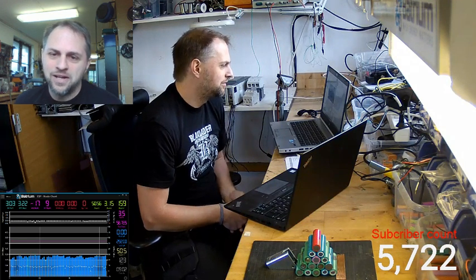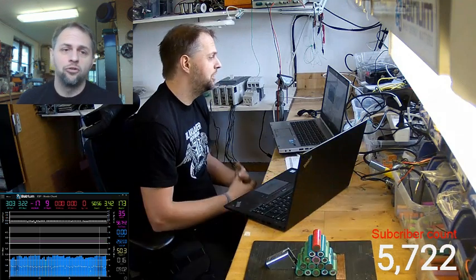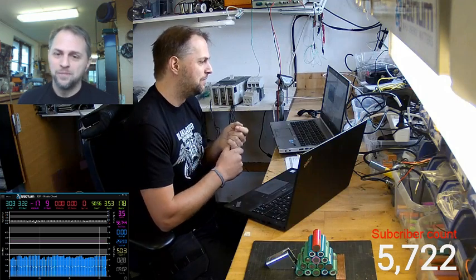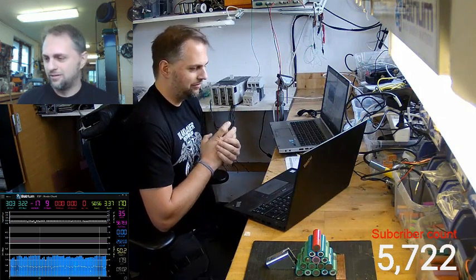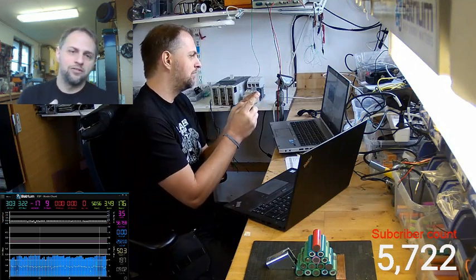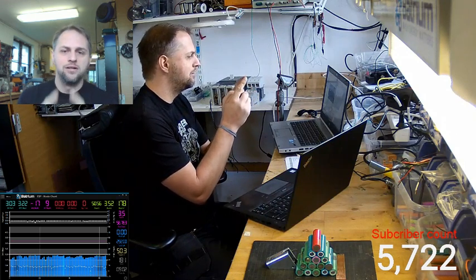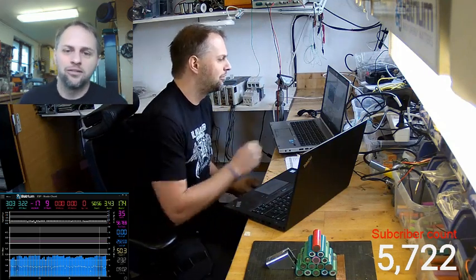The 48 volt APC UPSs are a lot easier to handle than the 192 volt. 48 volt in general is a lot safer to handle than above 150 volt. If you haven't looked into it on YouTube, search for Jacob's ladder and solar panels, and you will see that like 6 panels in series will create a spark, or this so-called Jacob's ladder, that is really long.